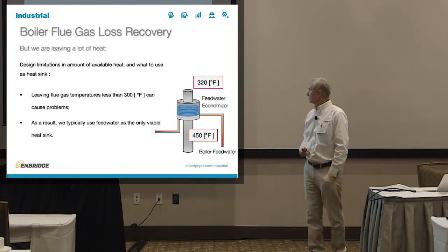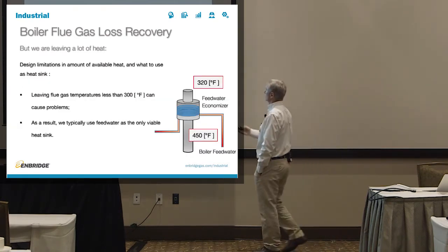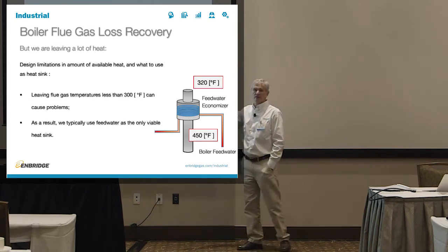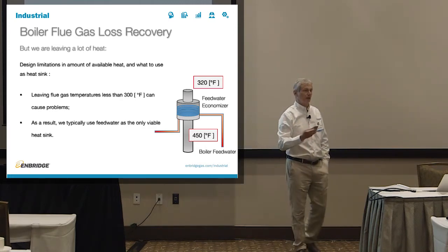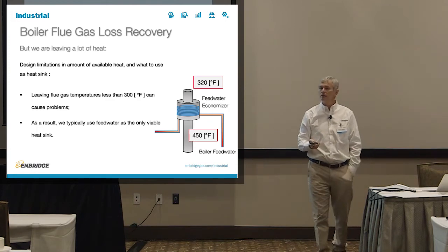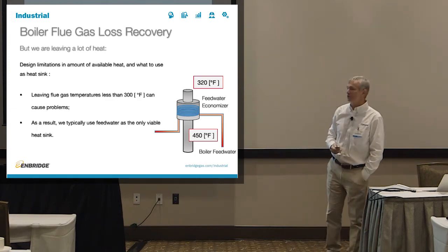The problem is, if you look at the sketch here, you go from 450 to 320 degrees F. 320 degrees F is still a considerable amount of heat. So you're leaving a lot of heat on the table with a feed water economizer.